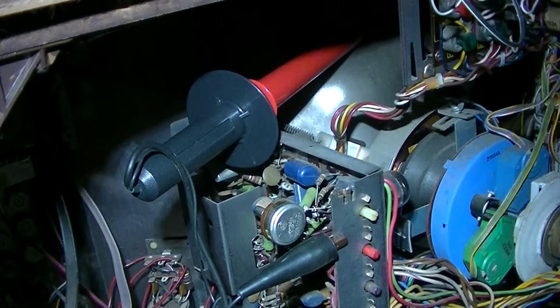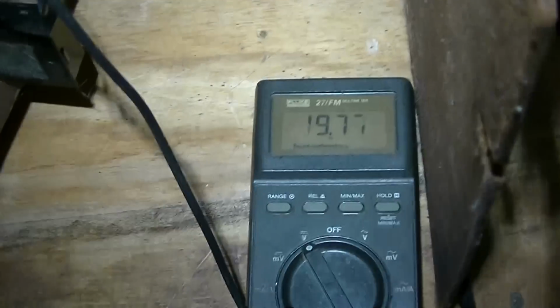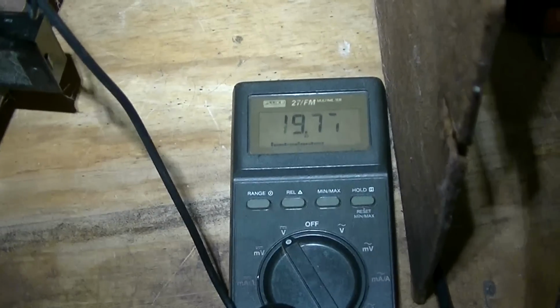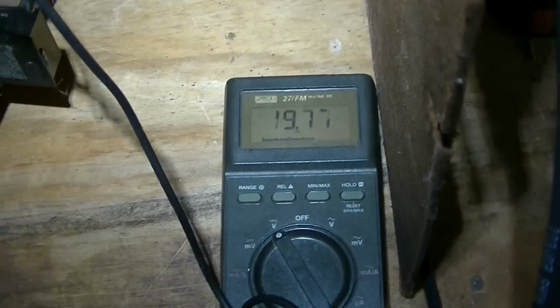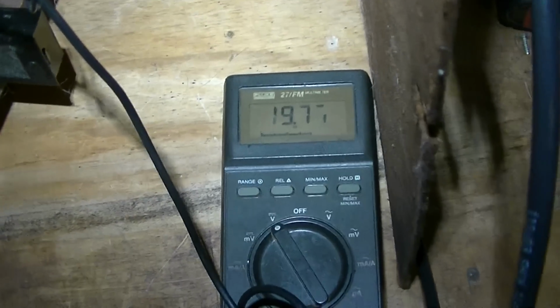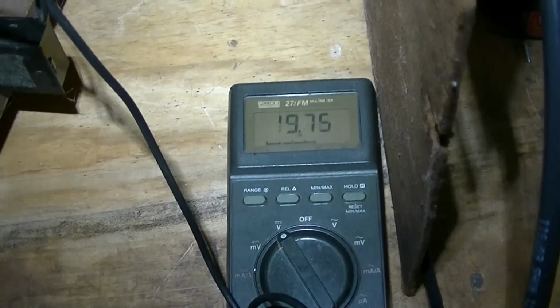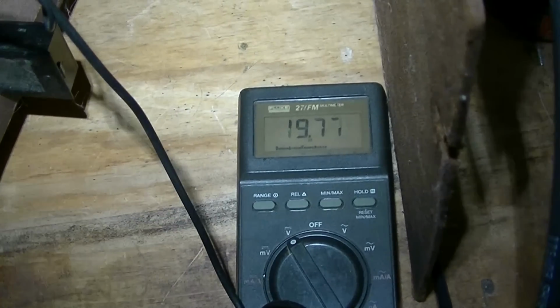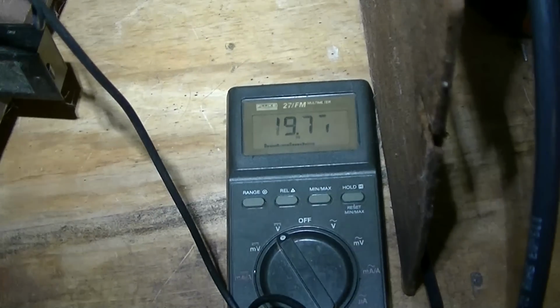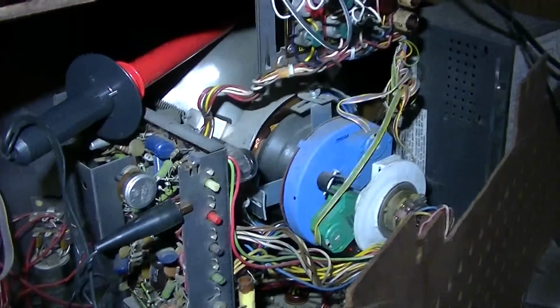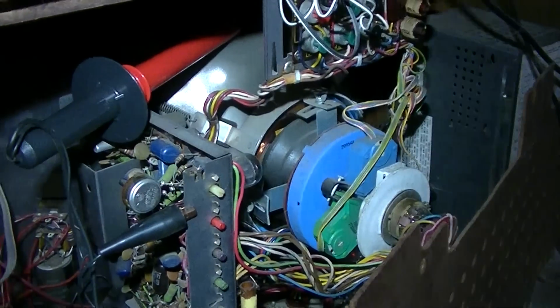So I had the high voltage set at 24 kilovolts using this exact probe and meter, and the high voltage has dropped about 5 kilovolts. No wonder why it's soft and blurry. So no wonder why it's gotten kind of soft and blurry.